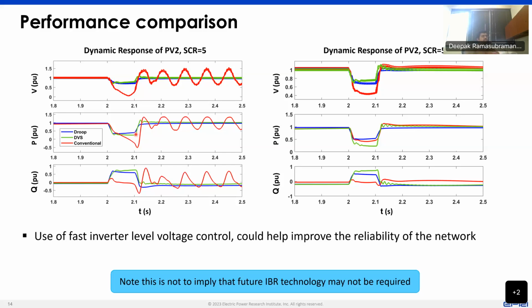An event occurs on the system. Can the inverter control maintain stability? Can it retain stability in the network? And we're not talking about a system going black and then coming back up. Now, this is not to imply that we don't want future IBR technology in the network. We definitely want improvements in control. We definitely want a different set of controls that might come in. But this is meant to show that there's probably a lot of capability in our existing inverters that is not fully utilized. And if we do utilize it, we can improve the way in which we operate the network. We can go one step further towards a higher percentage of inverter-based resources.